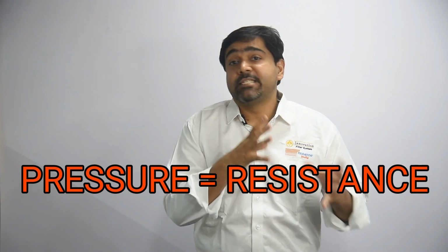Pressure and flow rate go hand in hand. They are like two peas in a pod. Now, in designing your filtration system, you need to know this relationship between pressure and flow. Pressure is basically resistance. Understanding this relationship becomes even more important while choosing pumps for your filtration system. Many times it is misunderstood that a pump is a pressure generating device. No, a pump is basically a device to overcome the resistance generated by the system.